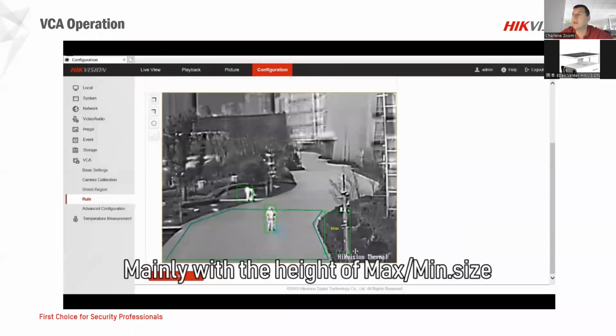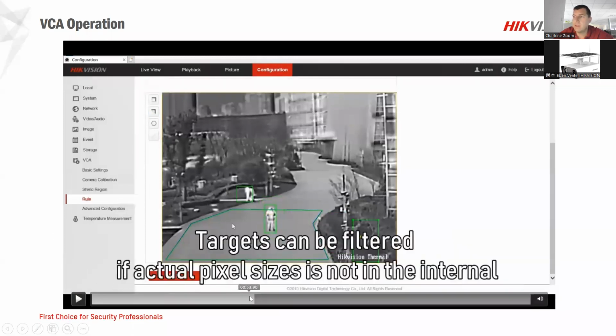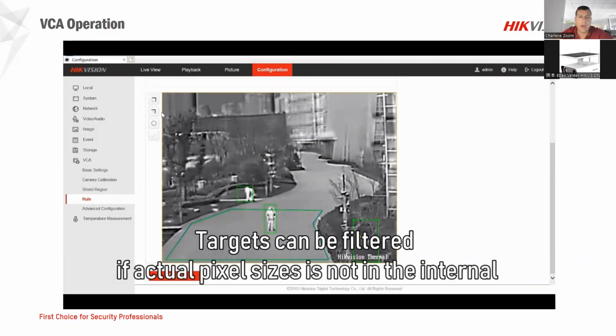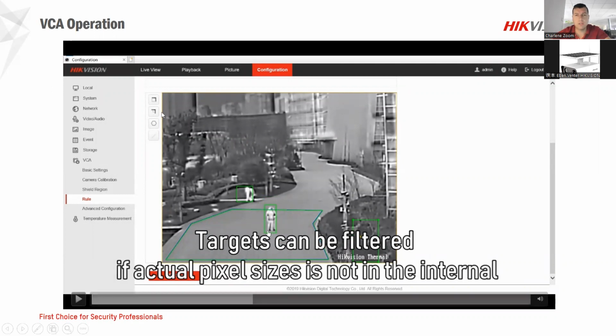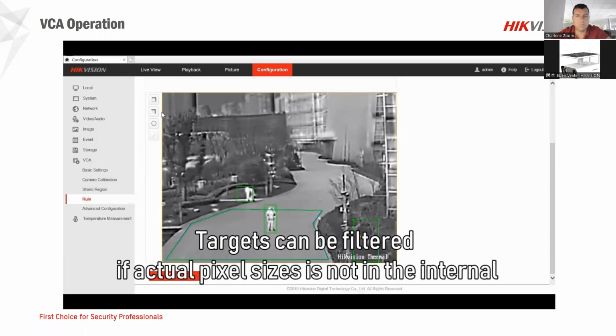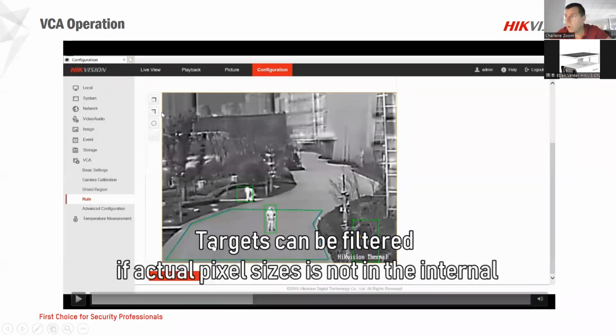So this tool is very nice. And that is another thing to mention. When it comes to this type of setup, with the majority of thermography type of things and any thermo cameras, the best is to do the calibration, if you want to call it calibration, is to set it up. Right, you need to have that person straight in line of that view and as close as possible. Put a person there, draw your minimum, draw your maximum. That is going to reduce your false alarms or your notifications quite a bit. This setup is a lot of homework, so it needs to be done correctly.